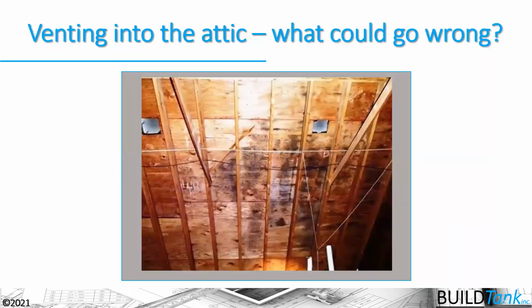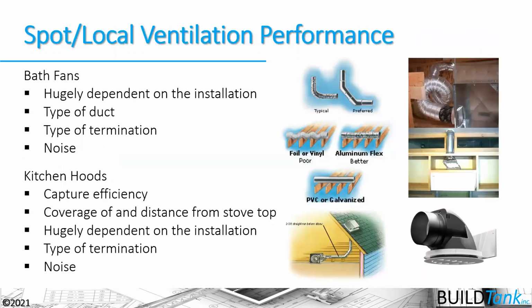And if we don't duct it all the way to the outside, we're going to get potential moisture buildup and molds and other things happening inside our buildings or up in the attic on the underside of the roof sheathing and whatnot. So getting that spot ventilation system ducted all the way to the outside is super important. And a lot of the fan manufacturers, specifically Panasonic and Broan, have really good installation instructions for how to install the duct that's taking that air from the fan to the outside.